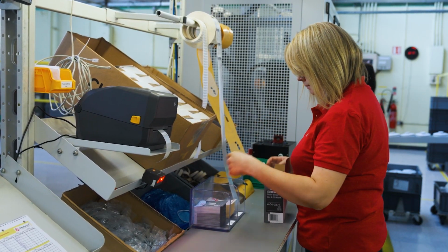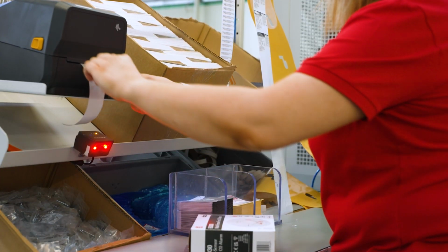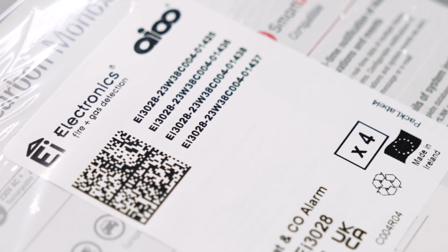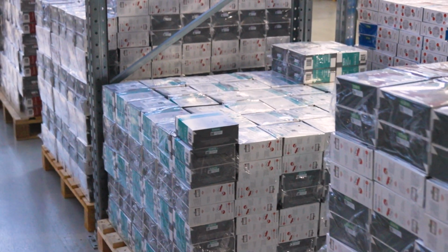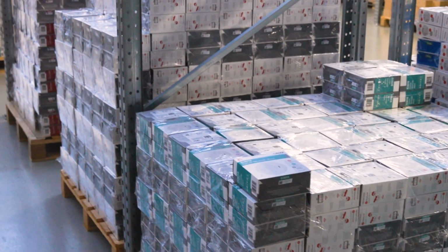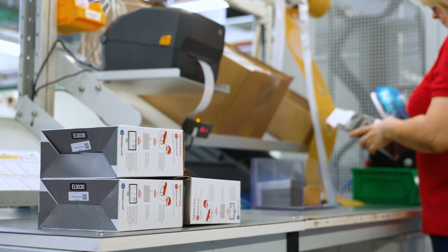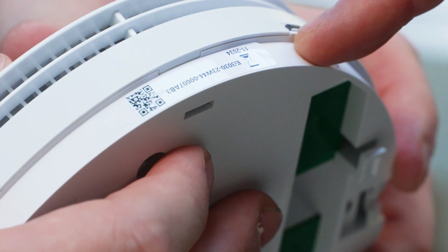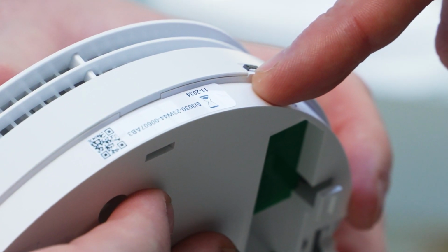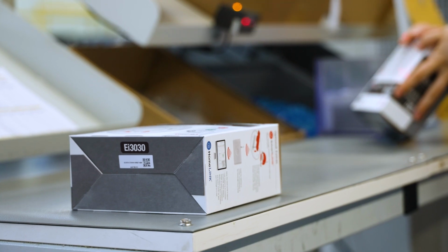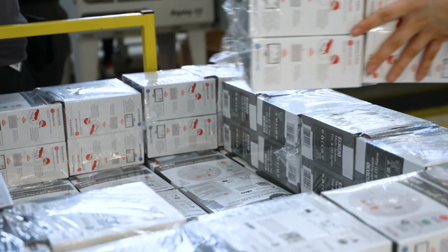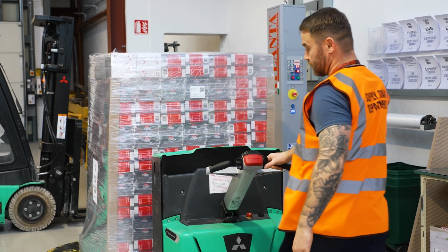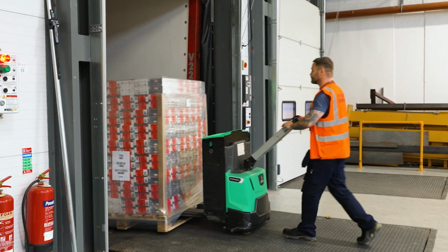It then moves to the pack station. This is at the end of the production line. The device will be scanned into the pack station using the serial number provided by the device. If a device at this stage has not passed all of the prerequisite tests, a pack label would not be printed. It's important to add that level of traceability here, because it's impossible to print a pack label for a device that hasn't passed all of the defined tests in the process before making it to the pack station. It's assigned a pack label. It's then packaged into its box. Pallet is shipped to our warehouse, and from there it forwards on to Oswestry, to Aico.